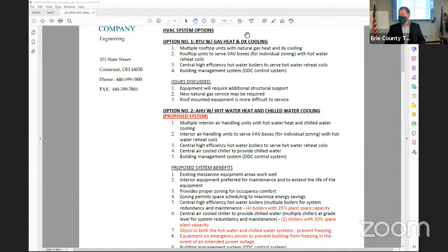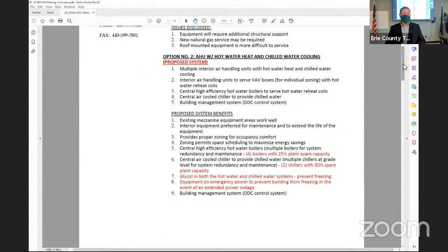On the cooling plant side, we were looking at 2 chillers exterior to the building on grade level. So we would not have to endure any cost associated with additional structural framing up on the roof. Keep the chillers at grade level so that they're easier to maintain. And we were looking at 30% spare capacity in those. So the chillers are sized for the warmest day out of the year, which usually falls in July or August timeframe. Typically, you may only be running on 1 chiller, so you have that other chiller almost for full redundancy.